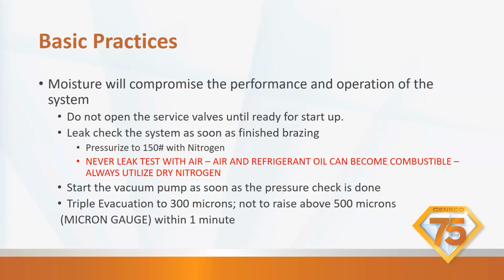Moisture will compromise the performance and operation of the system. Don't open the service valves until you're ready for startup. Leak check the system as soon as it's finished brazing. Pressurize it to 150 pounds of nitrogen. I know some guys use more. I took that right out of the book.